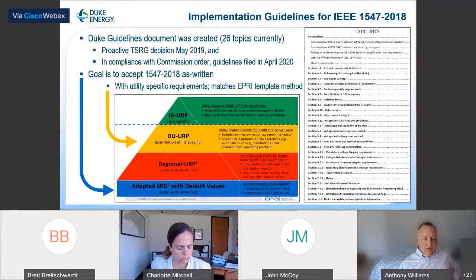The next level up is a regional level for RTOs or ISO requirements or specific settings they may have, which would not be an issue for Duke. The yellow layer is the utility-specific guidelines that account for how the system is designed and operated—many utilities have specific requirements here to address their unique systems. The top of the pyramid indicates there could be specific requirements unique to just one site, which is the crossover point from utility guidelines to specific DER settings.